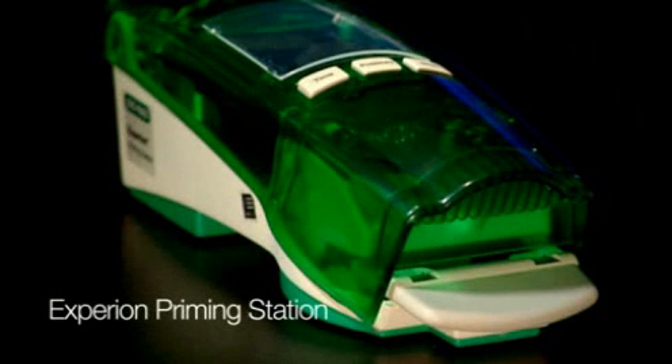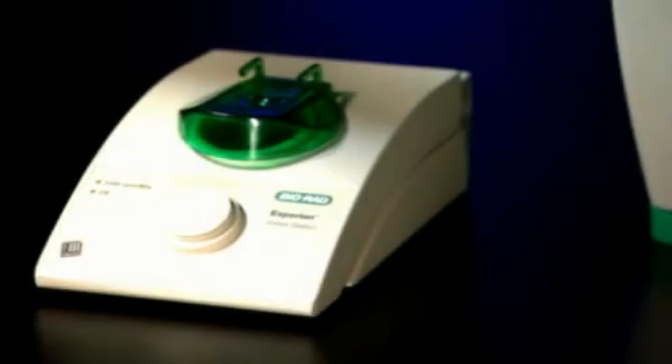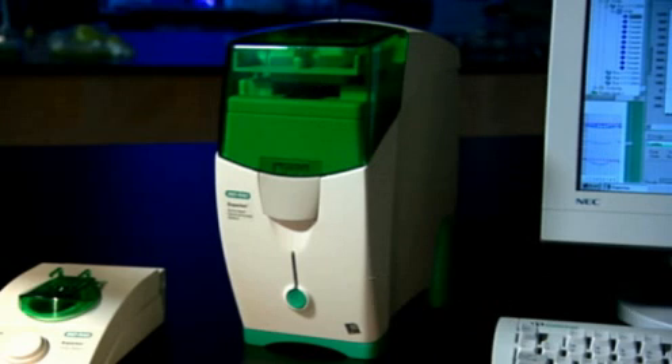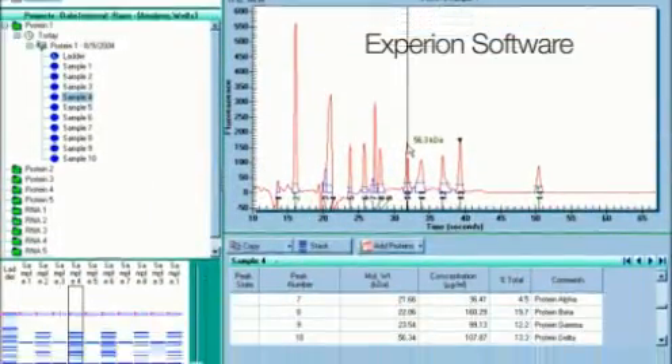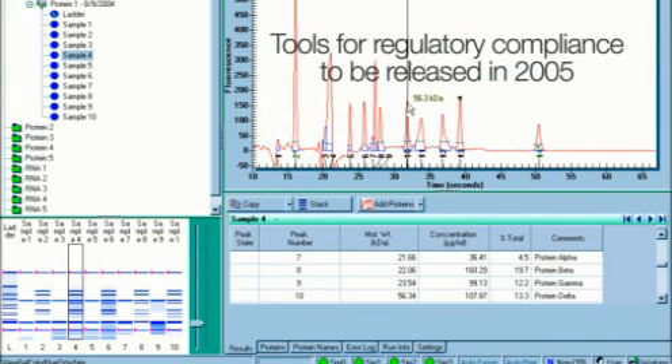The automated priming station uses preset time and pressure settings to ensure consistent priming of the gel into the chip microchannels. The vortex station secures the chip during vortexing to guarantee thorough mixing of the RNA analysis reagents. The automated electrophoresis station performs sample separation through to detection in one compact unit. And Experion software provides an easy-to-use interface to access experiments, perform analysis, and utilize tools for regulatory compliance.